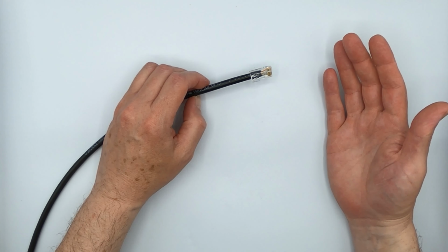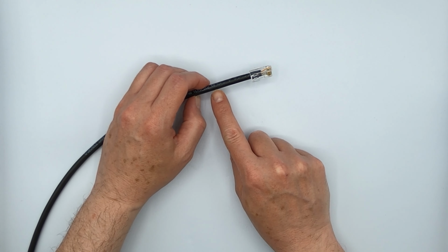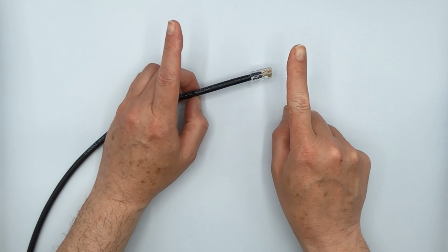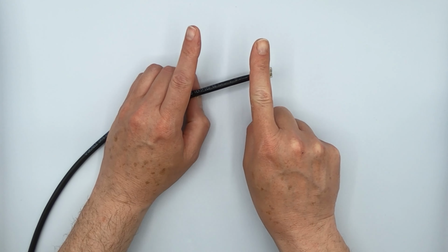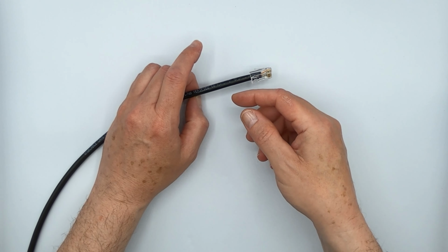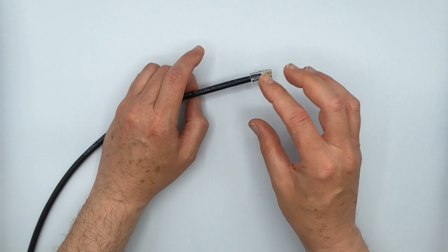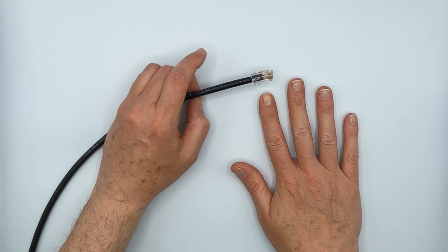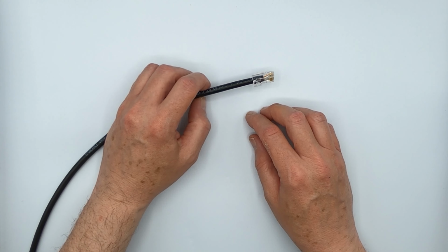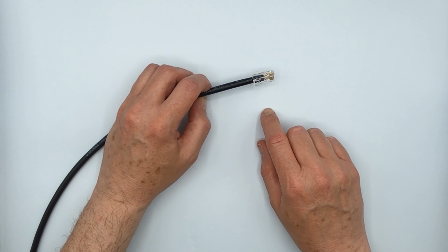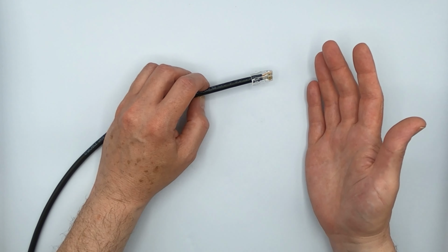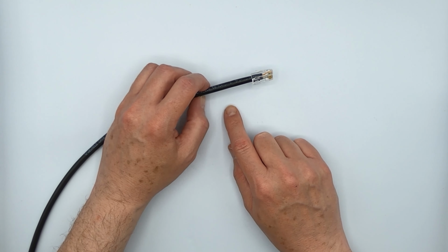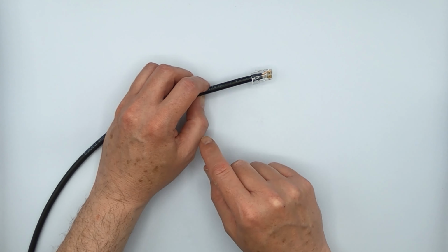The waterproof tape, if that particular cable jacket gets breached, will absorb the water that's coming in from outside to a certain extent. It'll stop it after migrating a certain distance, and then it turns into like a gel. And the gel is semiconductive, so it does impair cable performance to a small extent. Your cable will still remain working. But if you're looking for absolute bulletproof, no moisture can possibly affect its performance, and if high wattage PoE, 60 or 90 watt, is important to you, then gel filling is the way to go.